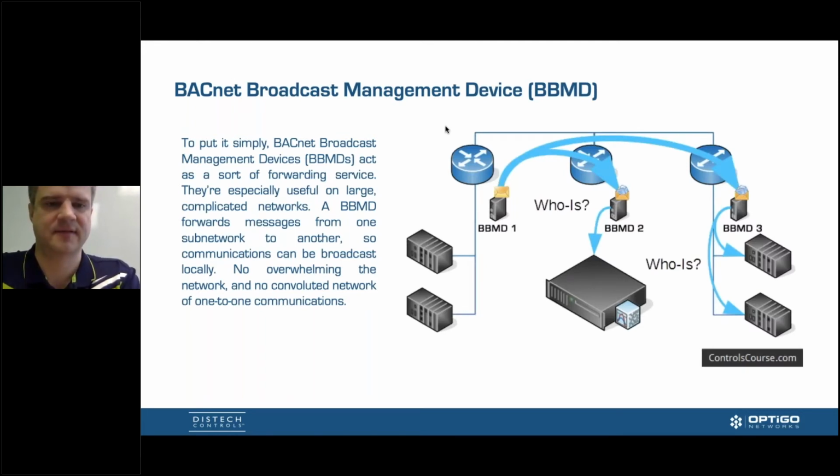And then we talk about BBMD. That's BACnet Broadcast Management Device. To put it simply, it allows you to communicate between different networks. That's the simplest way to think about this. This is remote buildings. It could be different floors. If you had set up different VLANs and you want to communicate through those, you would need either configured routers with tagging, where Robert discussed that on a previous webinar, or BBMDs that allow you to process the Who-Is command, and that Who-Is will allow us to discover all of those devices on the network.